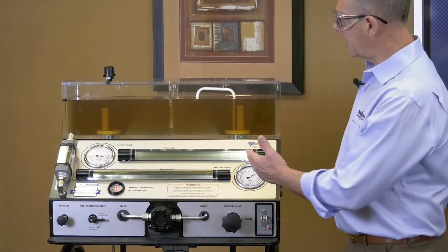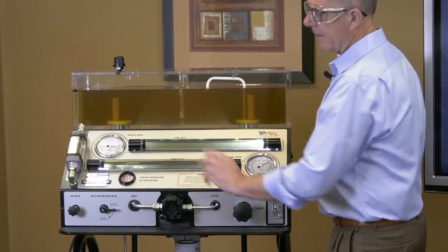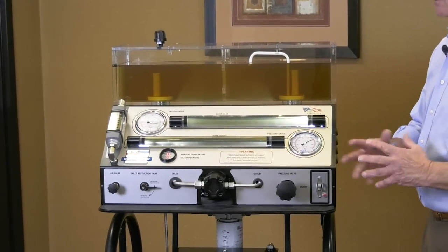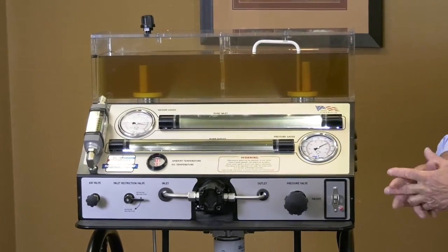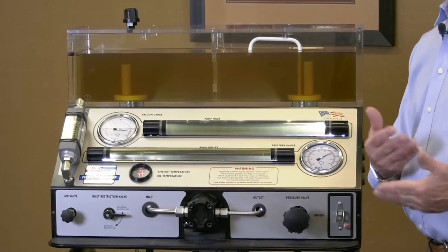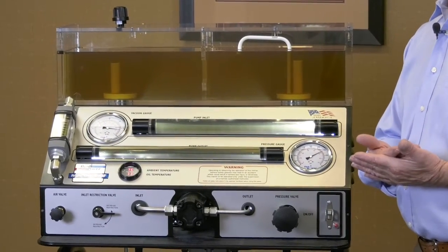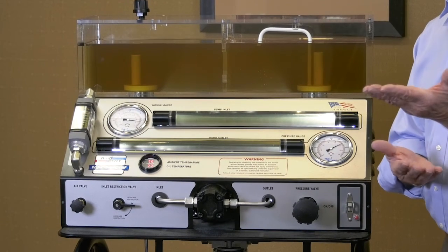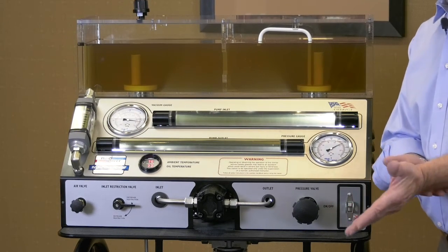Again, we can see that there is no evidence of cavitation. So that is my point of reference. Now we're going to simulate a condition whereby my inlet restriction inexplicably drops down to, let's say, 1.